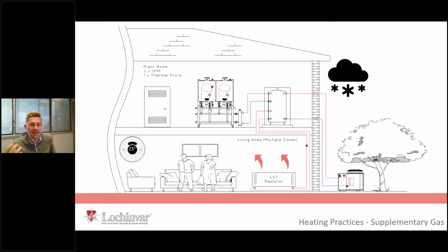So when you take into account that initial capital expenditure, if you have got a site which isn't just electric, it has gas elements, then actually heat pumps running as a base load product will allow you to bring down your capex quite significantly if you've already got the gas infrastructure. I wouldn't go out of my way digging a trench for a building so that you can give it gas for that purpose. But if you've got gas there anyway, or a commercial kitchen or something, it might be worth considering.